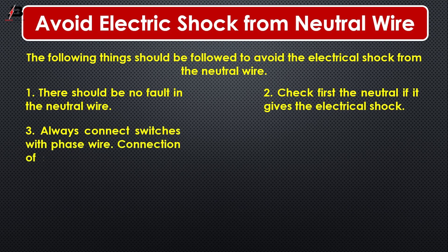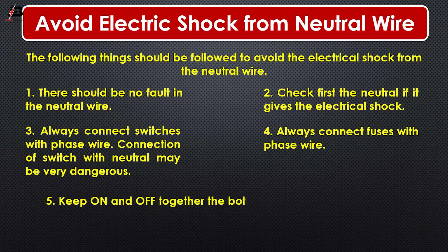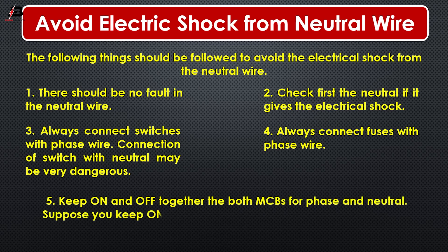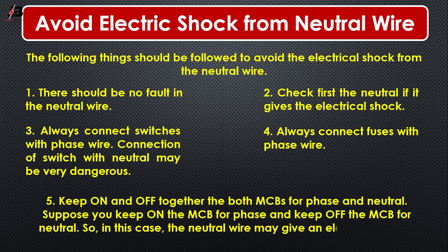Connection of a switch with the neutral wire may be very dangerous. Number 4: Always connect the fuse with the phase wire. Number 5: Keep both MCBs for phase and neutral on and off together. Suppose you keep the MCB for the phase on but keep the MCB for neutral off — in this case, the neutral wire may give an electrical shock.